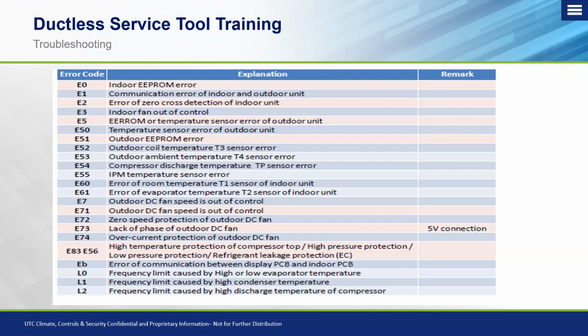So we talked about that. Okay, well, let me go see what that T5 is reading and make sure, hey, is the sensor out of whack, or am I actually dealing with a scenario where the system couldn't throw countermeasures to correct the overheating of the sensor, and I need to see what's going on. Do I have a dirty coil? Do I have an outdoor fan motor that's not working? Do we have a valve issue? Again, don't take the E55 and look in the indoor unit service manual, because you're not going to find it and it's going to confuse you.